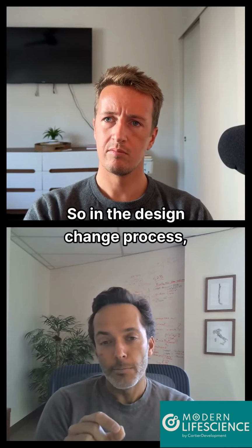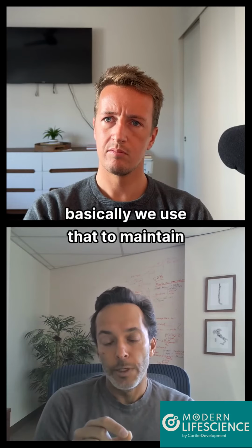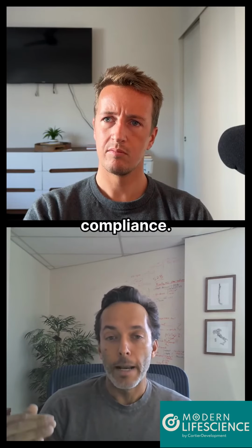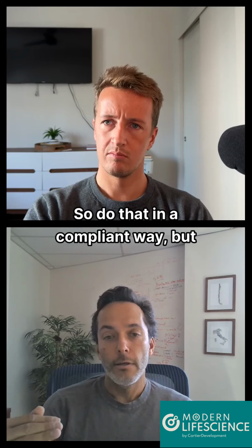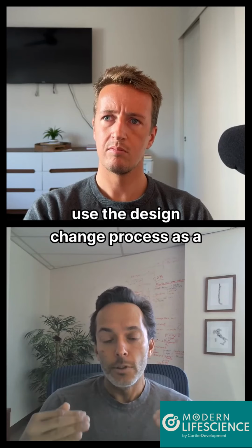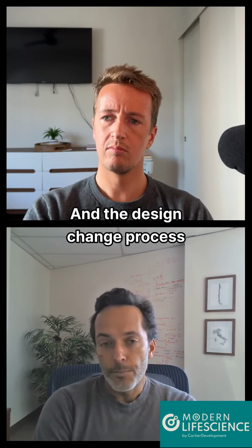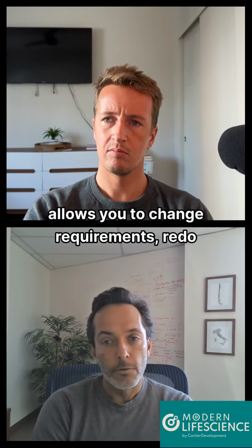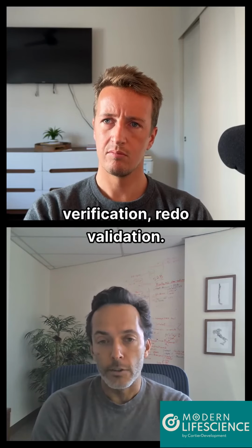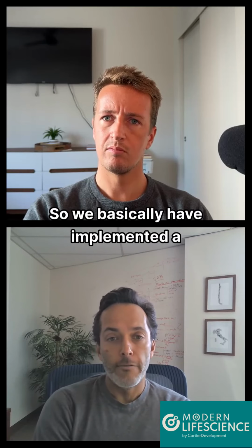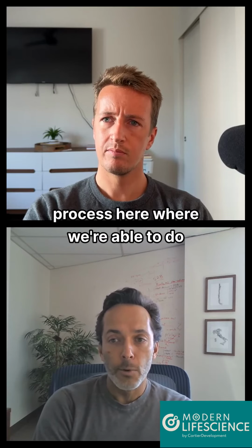So in the design change process, basically, we use that to maintain compliance. So do that in a compliant way, but use the design change process as a way to iterate into your product. And the design change process allows you to change requirements, redo verification, redo validation.